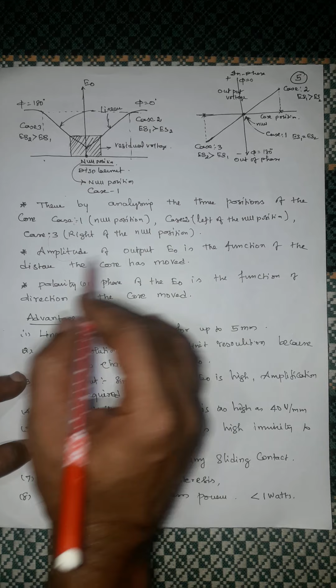Then we can see the output diagram. By analyzing these three positions, case 1, case 2, case 3, the amplitude of the output voltage E naught is a function of the distance the core has moved. This is the distance axis, this is the output voltage axis. There is a linear relationship between the output voltage and the displacement. That's why it is called LVDT, Linear Variable Differential Transducer. The polarity or phase of E naught is a function of the direction the core moves. The corresponding diagram is shown here.